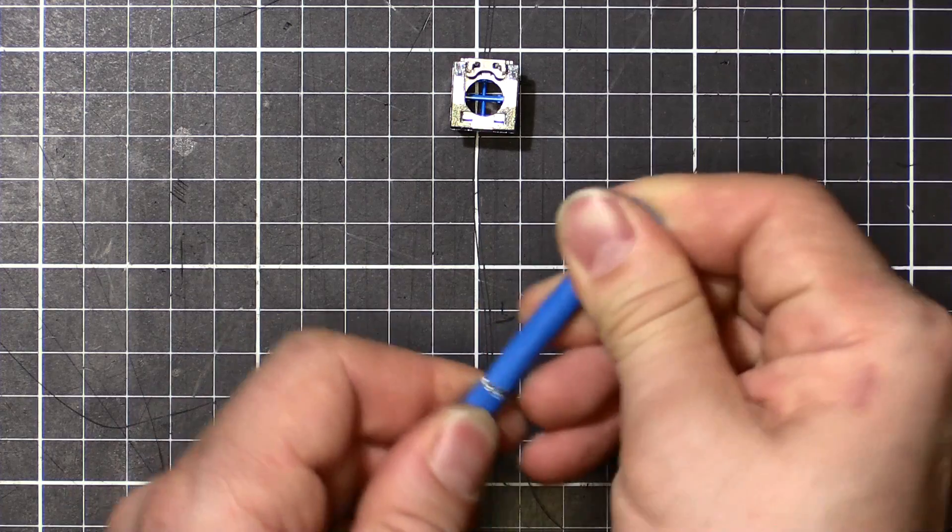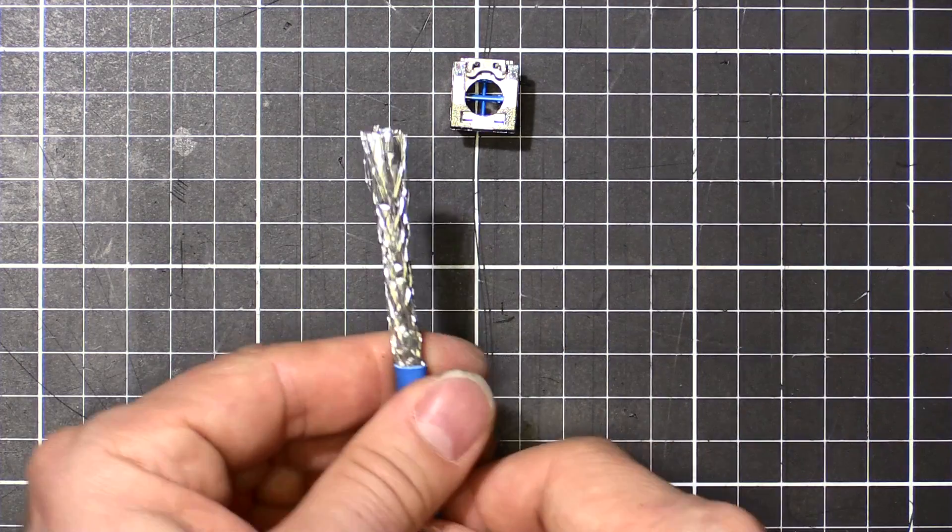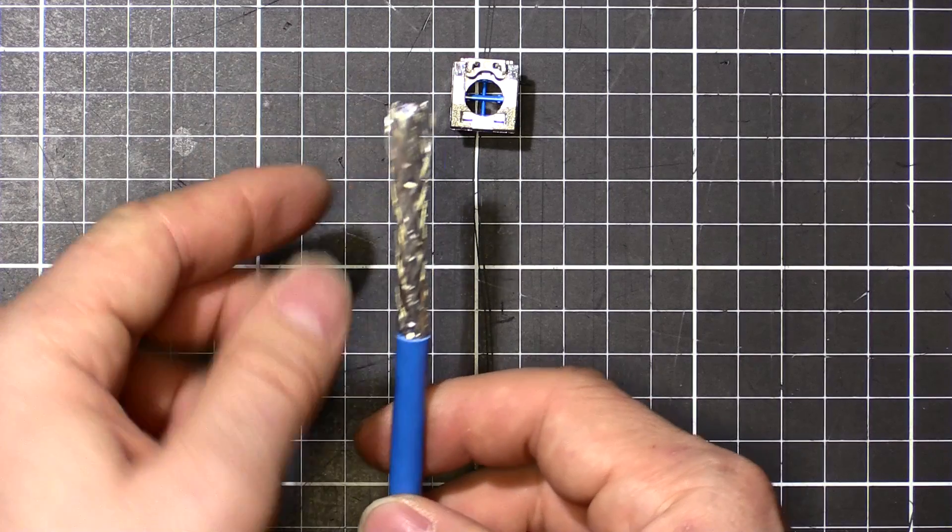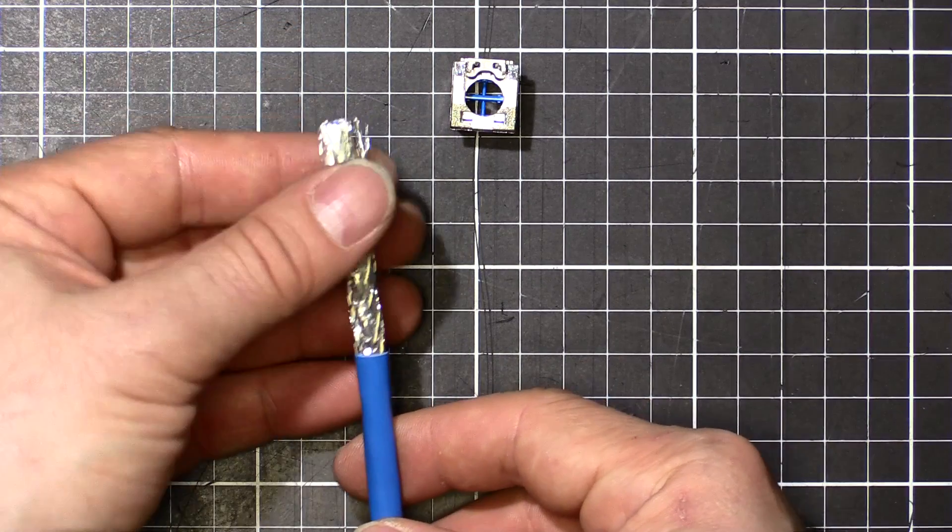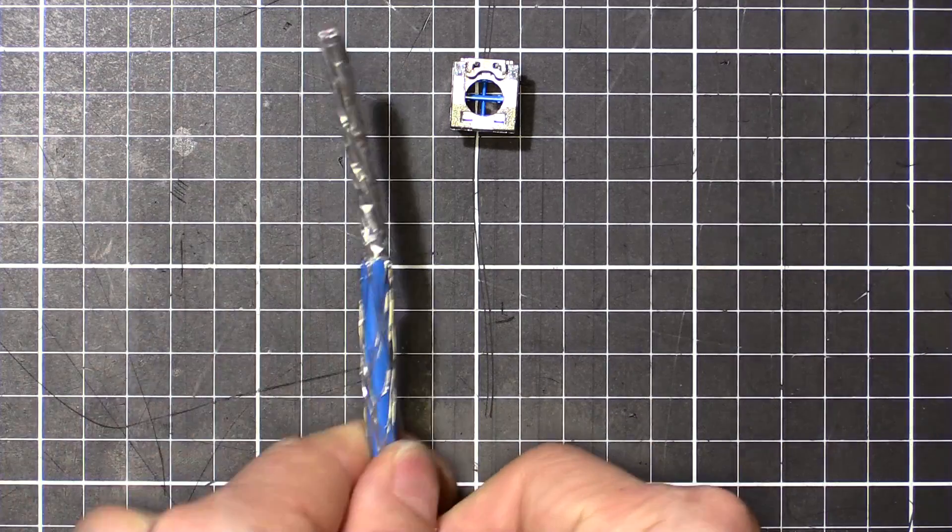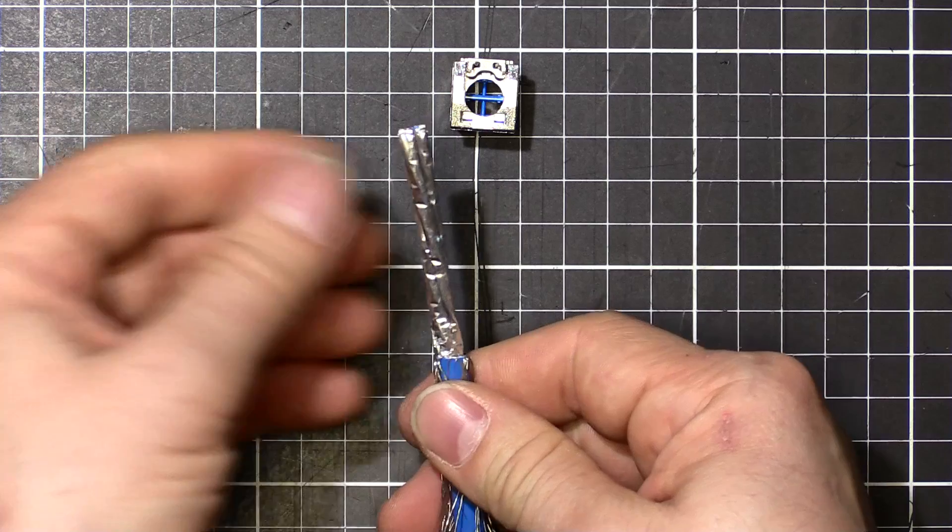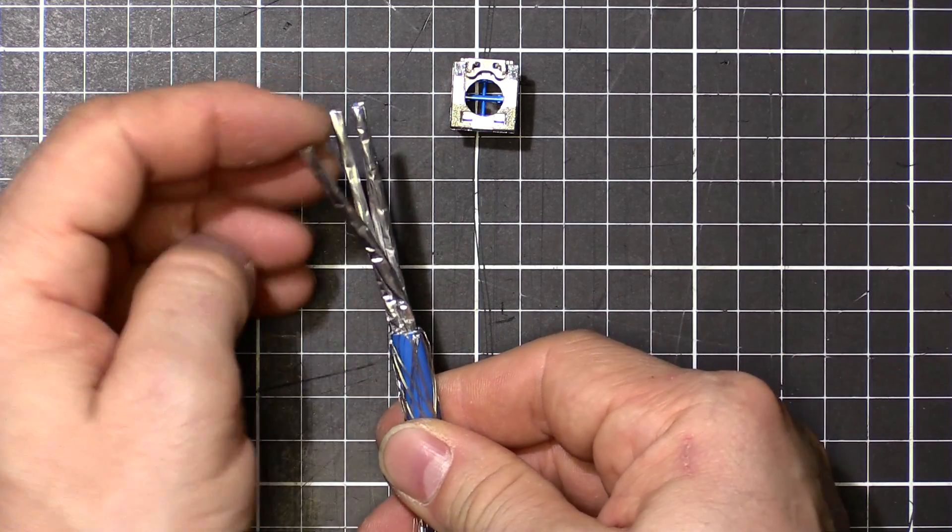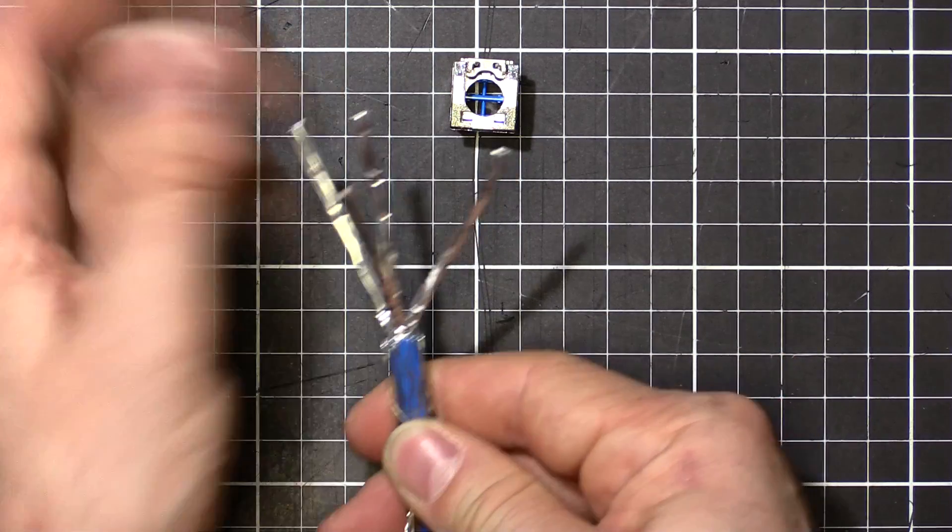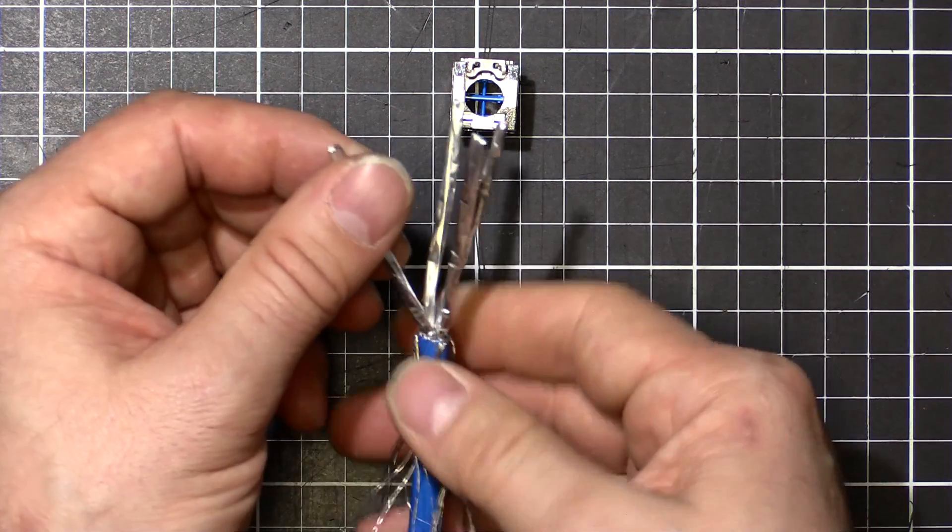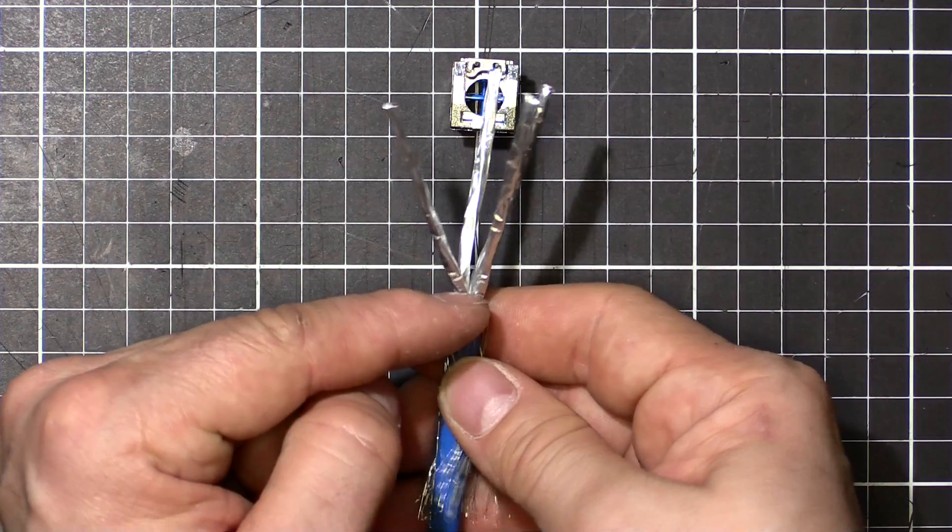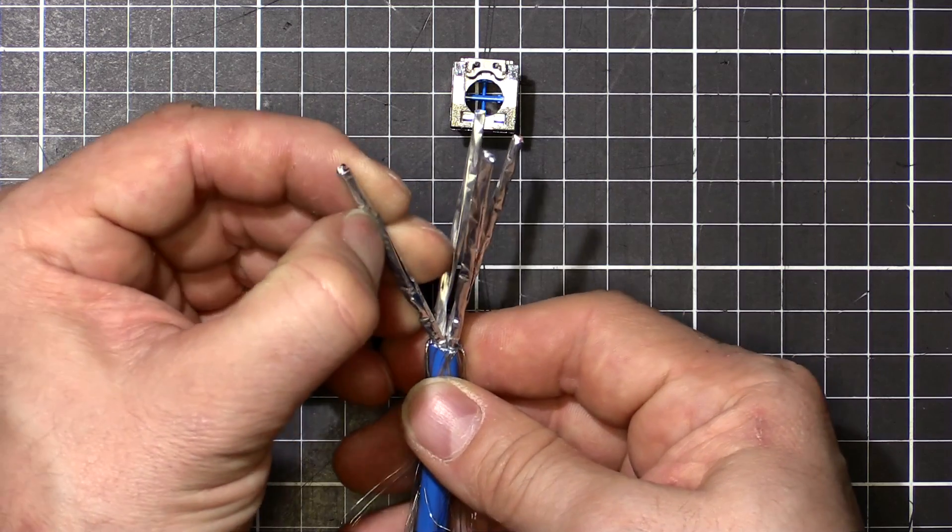We can just pull that up. Now you may have foil here, you may have braid. I've got braid. Whatever you've got, you've just got to fold it back, get that out of the way. And then, according to whatever cable you've got, you may not have shielded inner conductors. If you don't, that's perfect, you can skip this step. But if you do, we've got to remove this foil all the way back. I'll get rid of this foil out of the way.